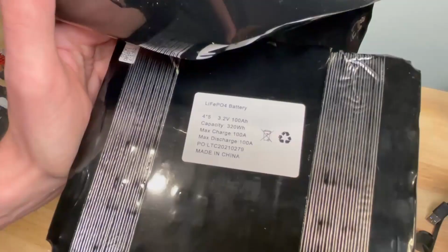What I'm worried about - I'm not worried about the battery, that's not gonna hit 65 Celsius under normal use unless there's a real failure scenario. That BMS might hit 65 if we're trying to do a 100 amp draw, and we'll find out because we're gonna do that. So they've actually got max charge and discharge as 100 amps.